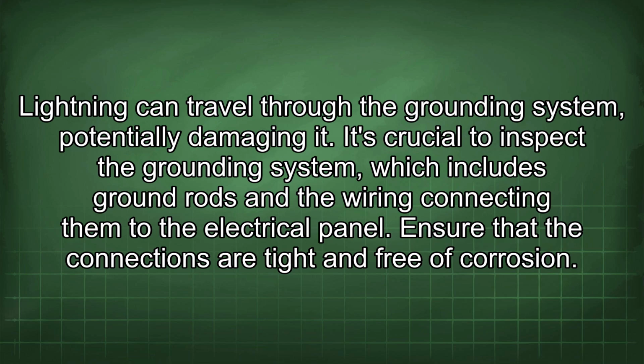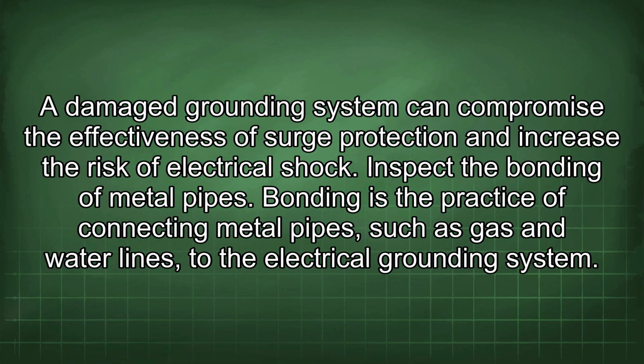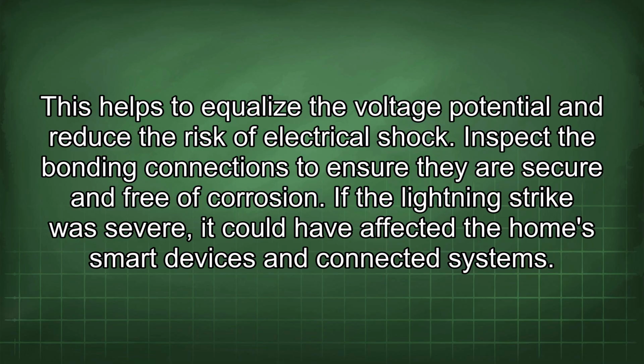It's crucial to inspect the grounding system, which includes ground rods and the wiring connecting them to the electrical panel. Ensure that the connections are tight and free of corrosion. A damaged grounding system can compromise the effectiveness of surge protection and increase the risk of electrical shock. Inspect the bonding of metal pipes. Bonding is the practice of connecting metal pipes, such as gas and water lines, to the electrical grounding system. This helps to equalize the voltage potential and reduce the risk of electrical shock. Inspect the bonding connections to ensure they are secure and free of corrosion.